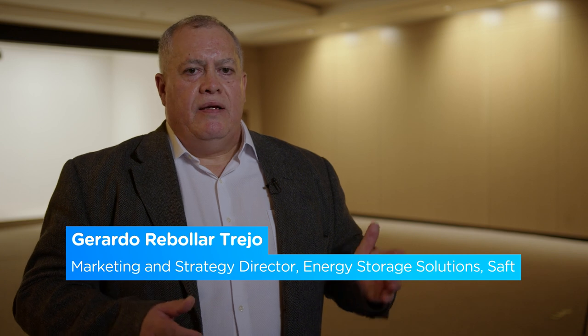The key advantages of lithium-ion batteries are several. One is the high density – today, batteries can reach up to 400 watt-hours per liter in a very dense pack. Another advantage is that they can live long – today, the life cycle is reaching up to 20 years. Another advantage is efficiency – today, lithium-ion batteries are reaching 98% efficiency, which means only 2% of the energy is lost in the process from charging to discharge. Also, lithium batteries are very cost effective.